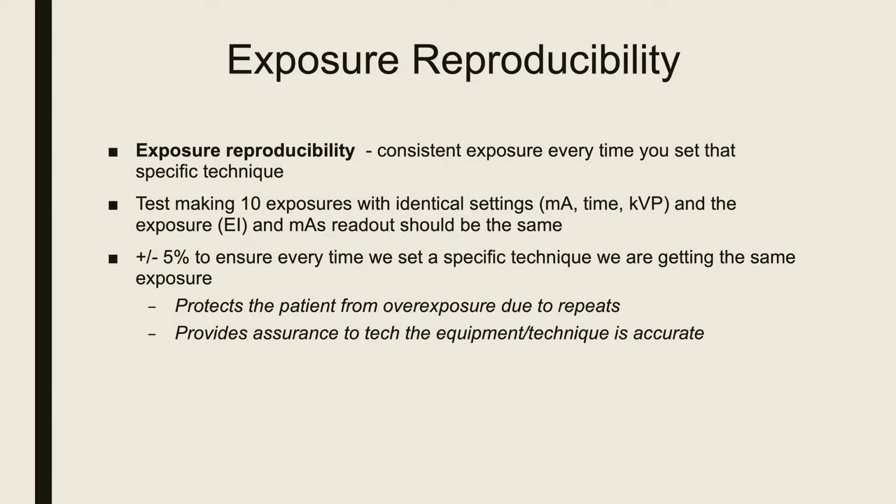It's a little bit tighter than MA linearity, because if you're making the same exposure over and over again, it should be the same. And this ensures that you're protecting the patient from overexposure, and that your technique is accurate.